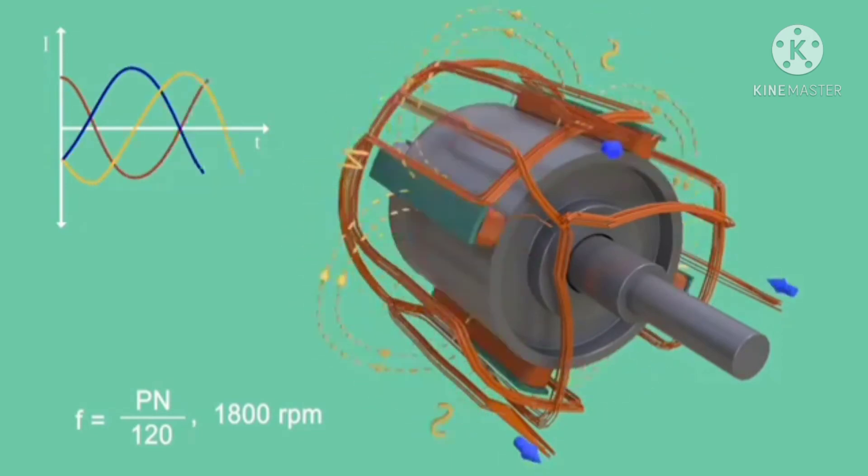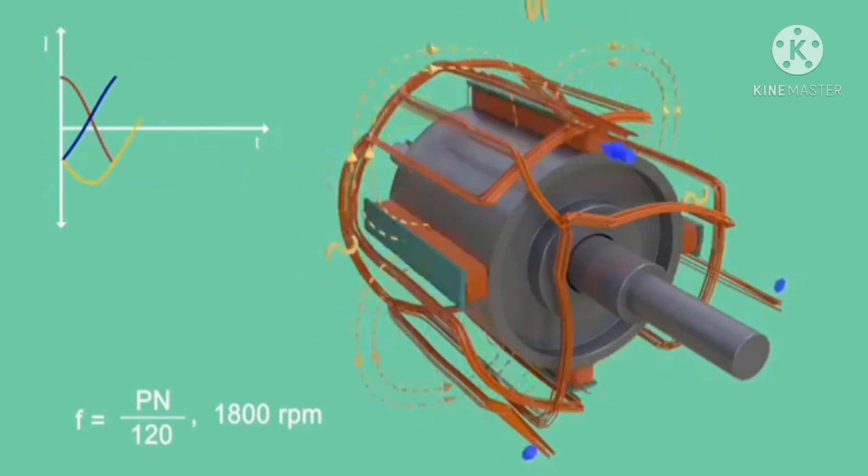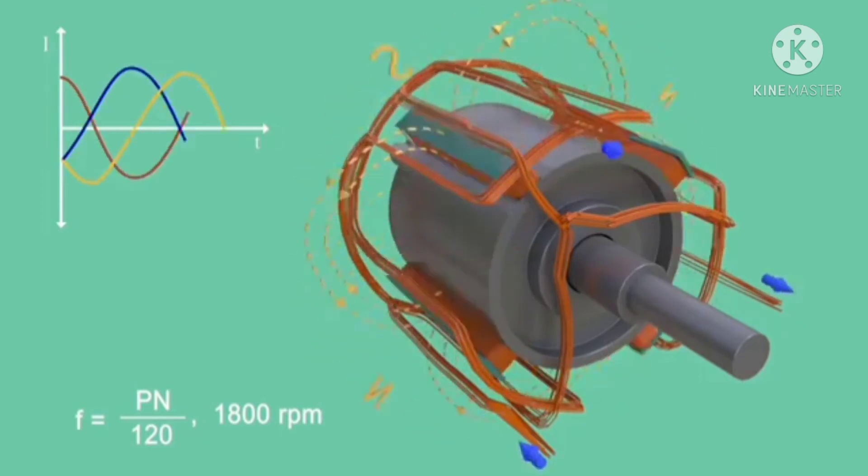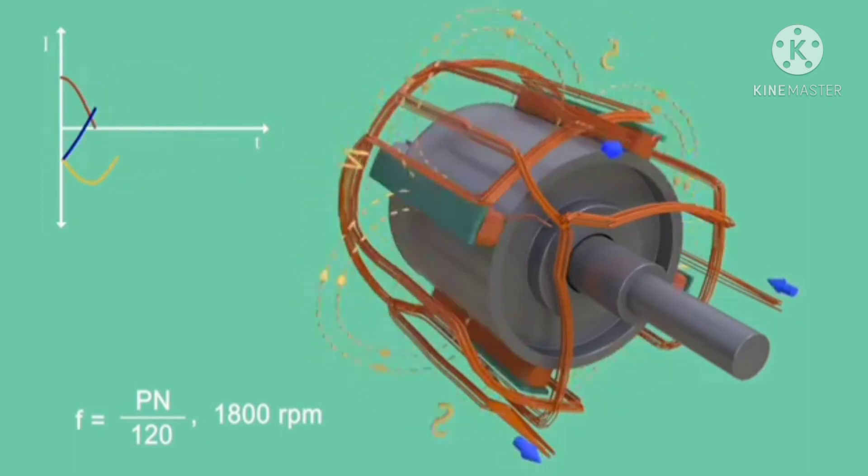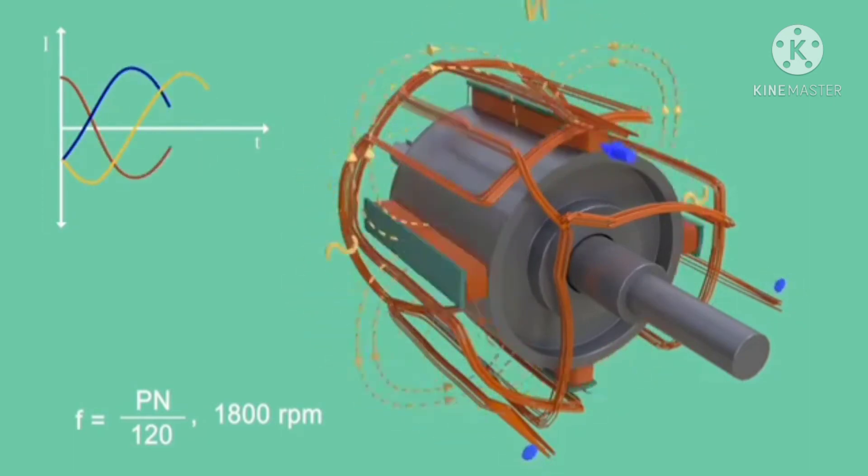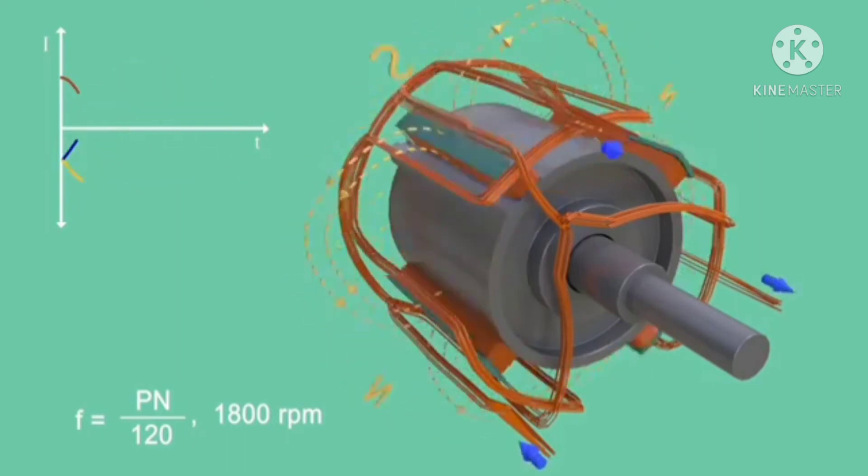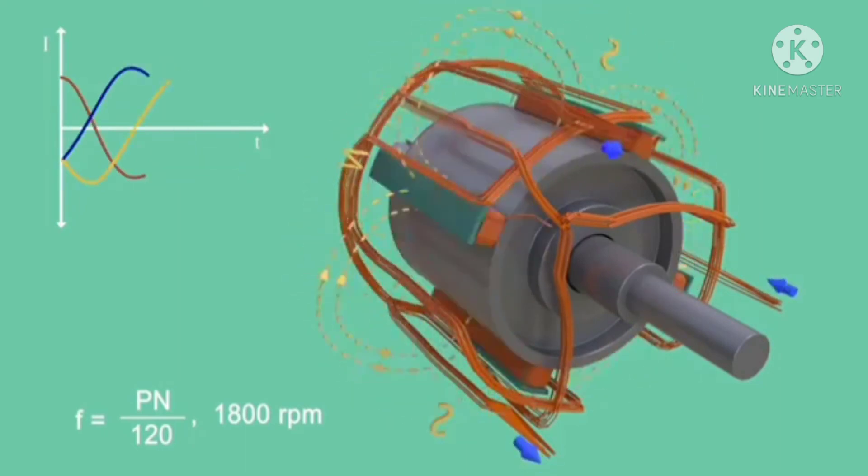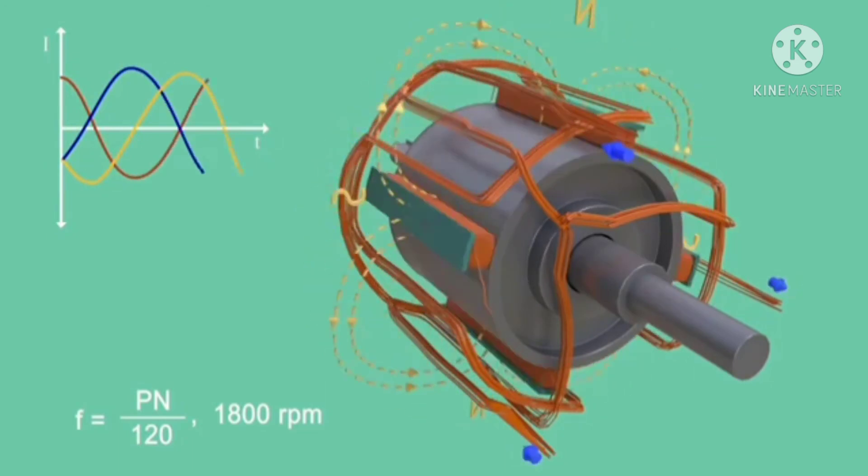So salient pole rotors generally have 10 to 40 poles, which demands lower rpm. Salient pole rotors are used when the prime mover rotates at relatively lower speeds, 120 to 400 rpm, such as water turbines and diesel engines.